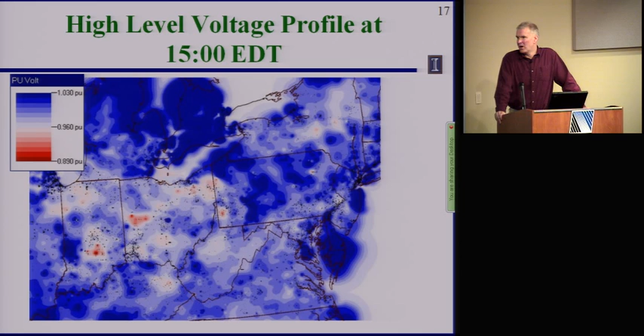This is a high-level voltage profile, best reconstruction of what the system looked like on August 14th at 3 o'clock in the afternoon. The red indicates low voltage areas. You can see the red dot in southern Indiana, which was because of the problem MISO was working on due to that tree contact. There was some lower voltage across Ohio, but it was not abnormally low. So there's been a lot of discussion and investigation about whether that red in northeast Ohio was permissible or not. Ultimately, the report concluded no, they were operating in a voltage insecure way.